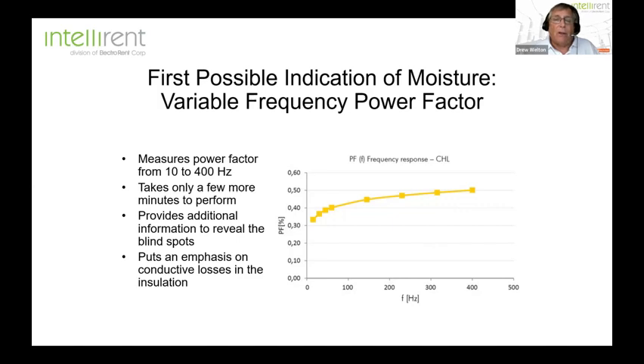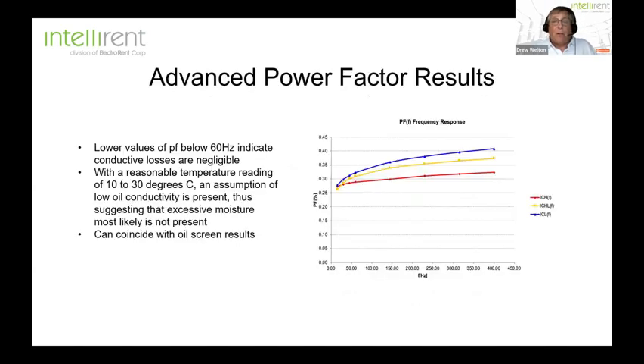Well, when we extend that range, it gives us some additional information to reveal what we refer to as the blind spots. It puts an emphasis on what we call conductive losses. Now, conductive losses can be a couple of different things. It could be sludge, it could be furans or inert ingredients, okay, but it can also represent moisture. So if we look at the lower values of the power factor below 60 hertz, if we see that these are lower in terms of your power factor measurement, that most likely indicates that we do not have any conductive losses. And if that coincides with your oil screen, your DGA results in terms of your ppm measurement, you're good to go. It's with all certainty, you really don't have a moisture issue in the transformer itself.